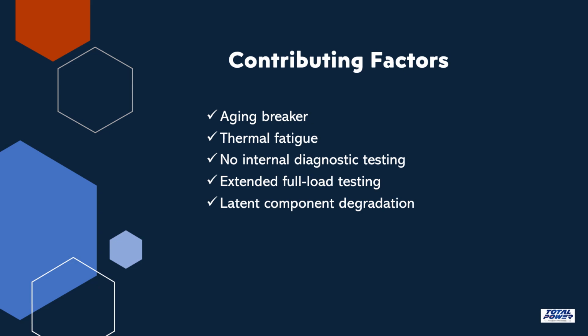Investigators also noted there was no predictive diagnostic testing completed before extended full load testing. Tests such as insulation resistance measurements and contact resistance testing may have identified deterioration before the event occurred.